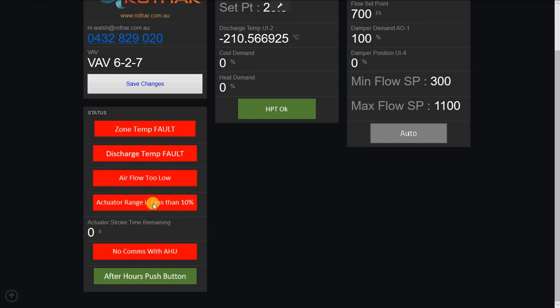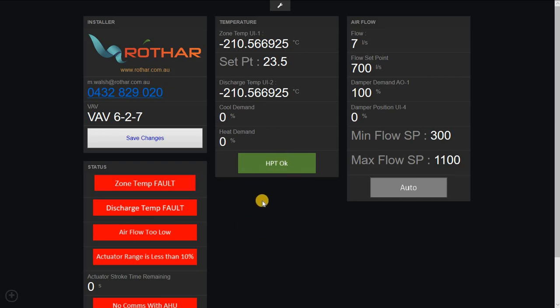So if the actuator fails its range, this is an extension of our auto stroking block, which we've made a video for. If the airflow is too low, if it's below a minimum set point, it will also generate an alarm. Discharge temp fault, zone temp fault, or no comms with the AHU will generate a fault. This fault represents itself on the sensor as an SOS, so 3 flashes, 3 blinks, 3 flashes, to advise, or at least to show people who know what they're looking for, that that's the VAV that is having difficulty. Also the HPT fault also contributes to that fault.